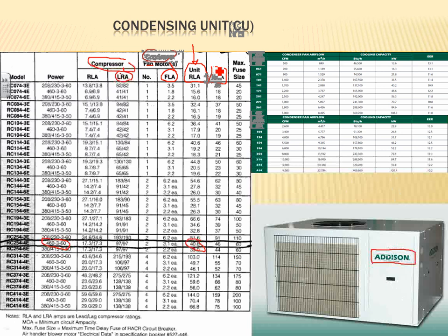The manufacturer guys size the ampacity for you, and they give you something called minimum circuit ampacity. This one is how you size your conductor, based on this value from the NEC code book. You size your conductor from minimum circuit ampacity. Done. And the sheet that I gave you is related directly to this.